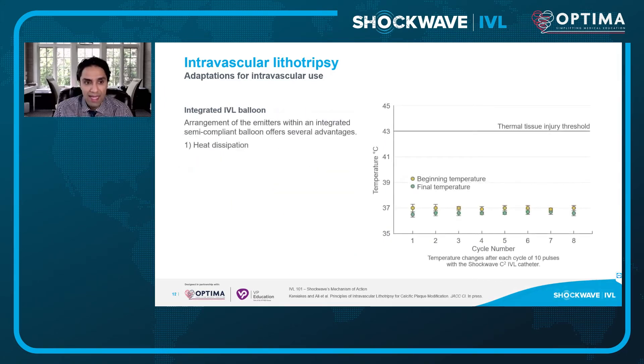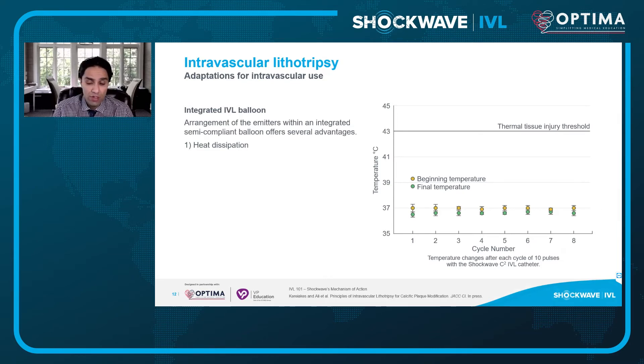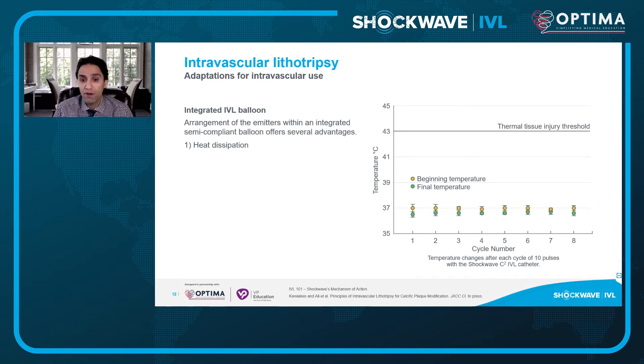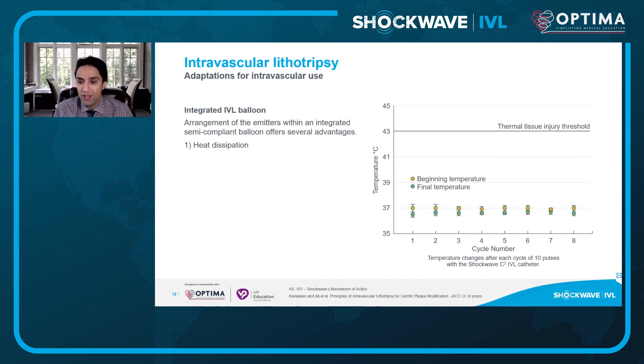Integration of these technologies into the balloon could lead to heat. One thing that needed to be engineered was ensuring we weren't creating charring or very high temperatures during arcing that could lead to a biological response within the artery. This was actually the first question received from funding bodies approached very early in the inception of IVL. However, temperature changes with each cycle of 10 pulses are really very small, within the standard deviation of even one degree Celsius. So temperature is not a factor, and heat injury of the vessel wall is not an entity here.